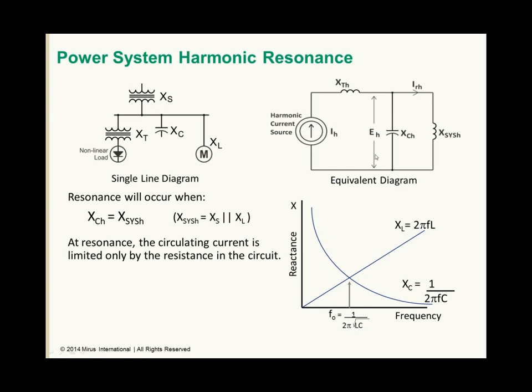Now, if harmonics are introduced to the system at that resonance frequency, a very little bit of harmonic voltage at that harmonic number will produce circulating currents between the power system components and the power factor correction capacitors. These circulating currents flow, and as they flow, they create voltage drops, which increase the harmonic voltage, which then drives more current, and that would increase infinitely, except there is some resistance in the system that's going to dampen that resonance somewhat.